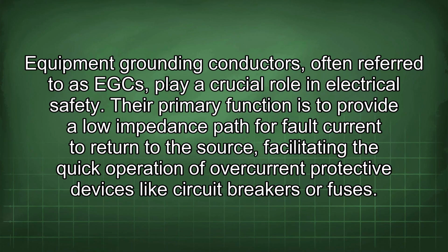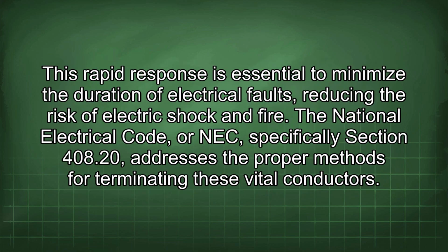Equipment grounding conductors, often referred to as EGC, play a crucial role in electrical safety. Their primary function is to provide a low-impedance path for fault current to return to the source, facilitating the quick operation of overcurrent protective devices like circuit breakers or fuses. This rapid response is essential to minimize the duration of electrical faults, reducing the risk of electric shock and fire.